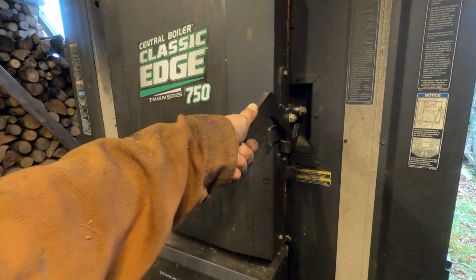So I'll see if the flame looks any different down here. Oh yeah, nice and hot. So you can see just on the other side of the flame, that probe, somewhere right there, is the one that we just replaced. So you can see the fire is hitting it pretty hard. And that's what that 1400 degrees is measuring.